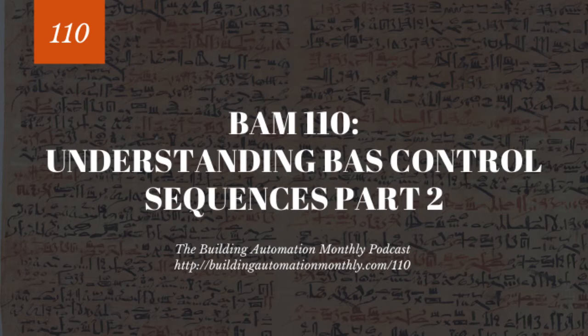Now, typically in common office rooms, you've got about 4 air changes an hour. So that's why if you change the temperature in an office space, for it to settle in takes a couple minutes, because you're having to mix all this new air volume in there to either cool down or heat up the air. That's why VAV units are what are called slow acting loops.